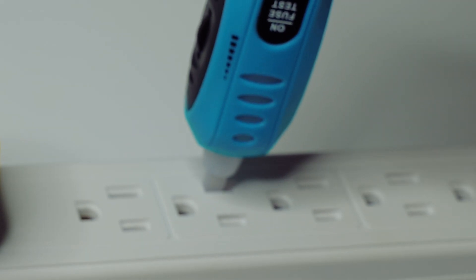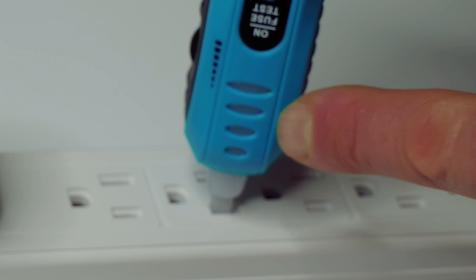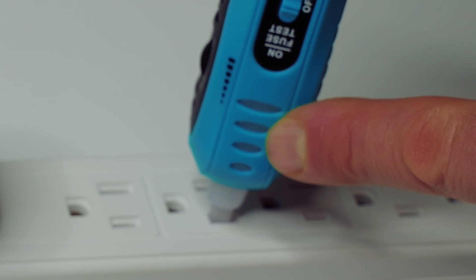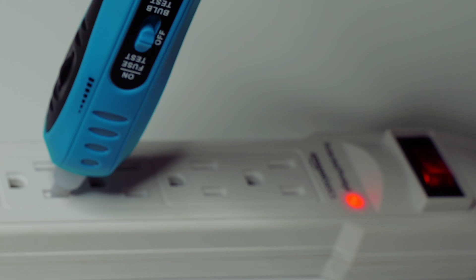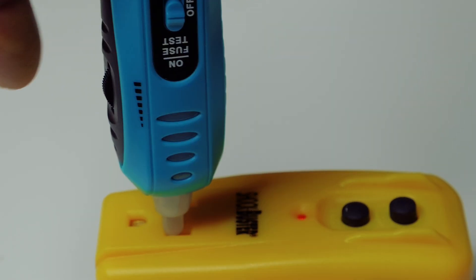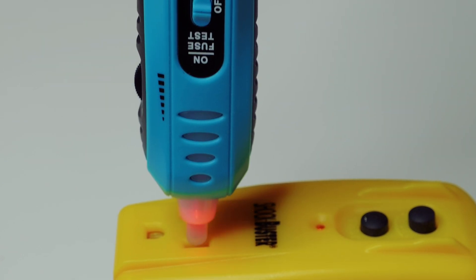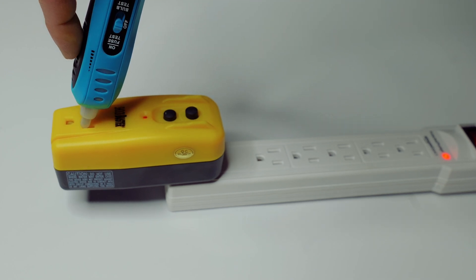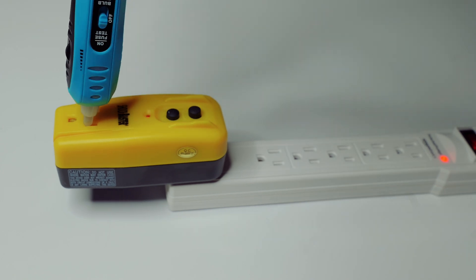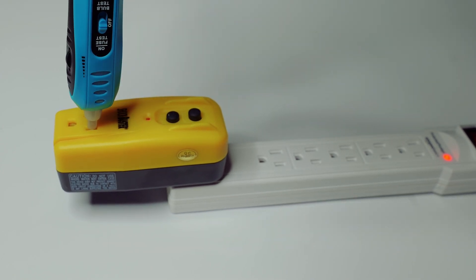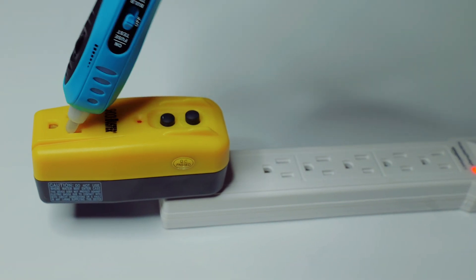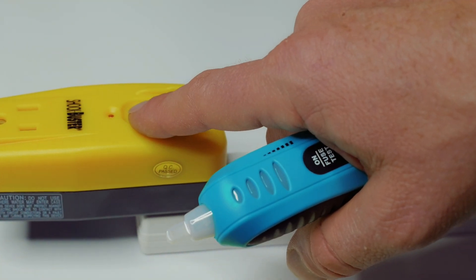So this is the neutral side. Of course you're not going to get any kind of light or beeping. Here's the hot side. Again no lights and you can't hear it beep. So this is actually giving us a false reading letting us know that we have removed power from this circuit. Again if this had been a high voltage power circuit this could potentially be deadly. Now let's move over to the socket buster. Again we're getting nothing. So with this sensitivity knob I've turned it up and with it all the way up like that you just have to kind of even be near it. You don't have to be in on these testers that have sensitivity knobs. While it's a great thing that you can adjust your sensitivity it can also bite you in the butt and tell you that you've removed power there and you actually have not. It's just a fact that your sensitivity knob is turned all the way down and that could allow you to work on a circuit that you think is de-energized but actually it is not.